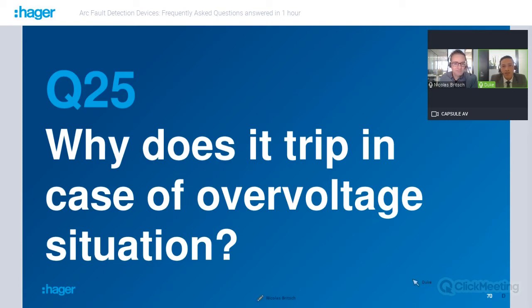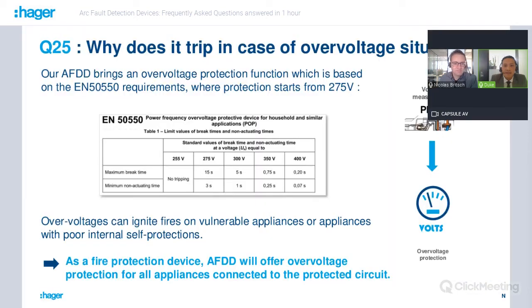So why does it trip in case of overvoltage situations? Our AFDD brings an overvoltage protection function, which is based on the EN 50550 requirements, where the protection starts from 275 volts. So the idea is that the higher the voltage is, the faster the product will trip.